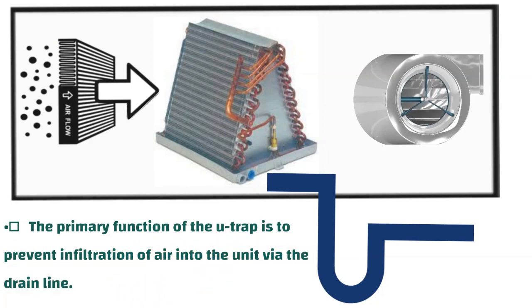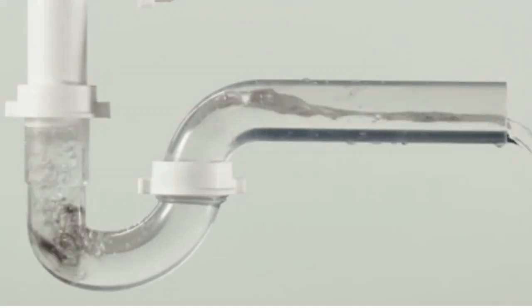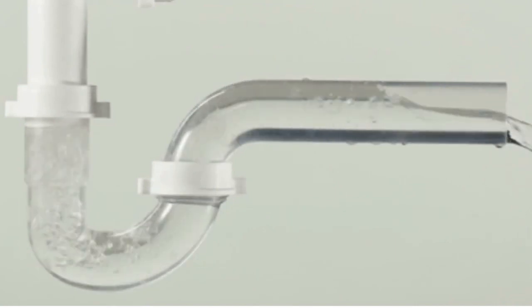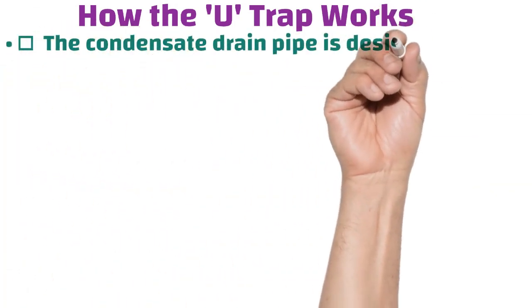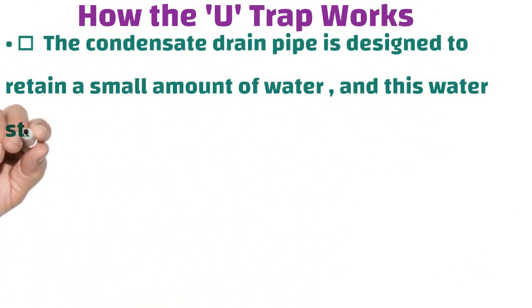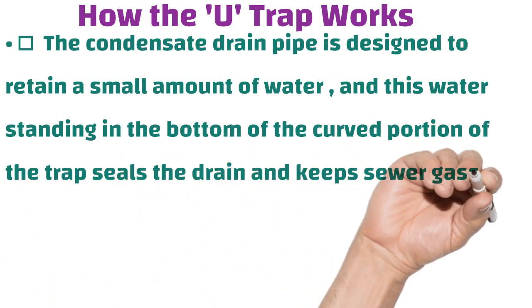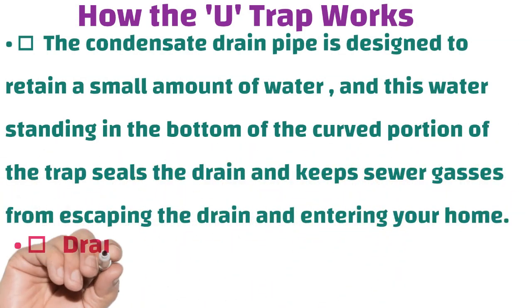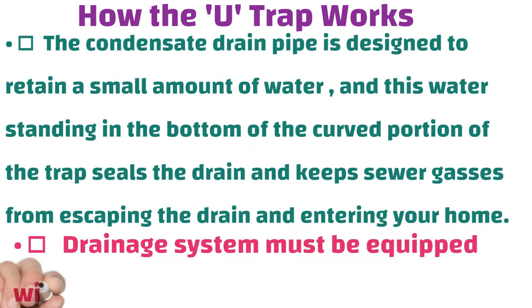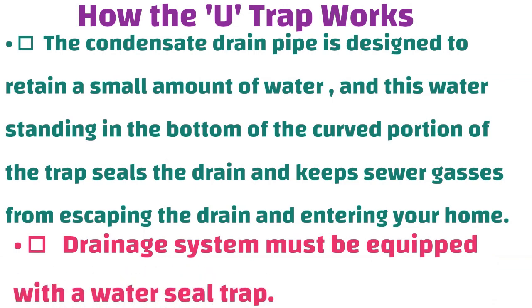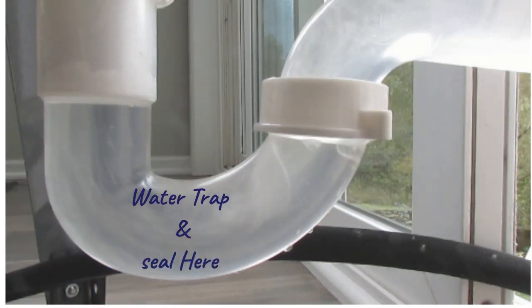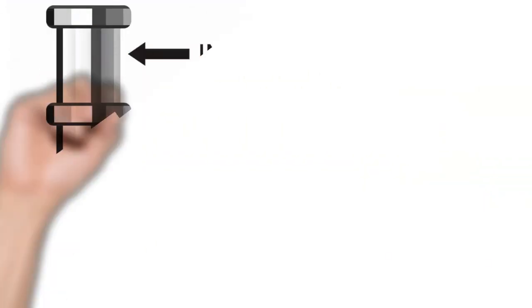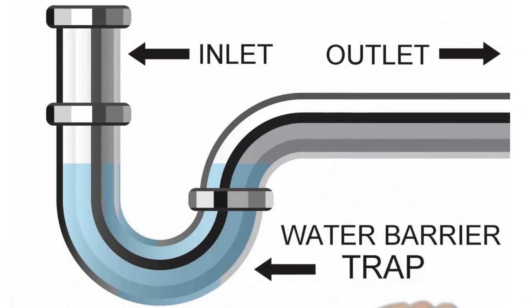How does the U-trap work? The condensate drain pipe is designed to retain a small amount of water. This standing water in the bottom of the curved portion of the trap seals the drain and keeps sewer gases from escaping the drain and entering your home. The drainage system must be equipped with a water seal trap.